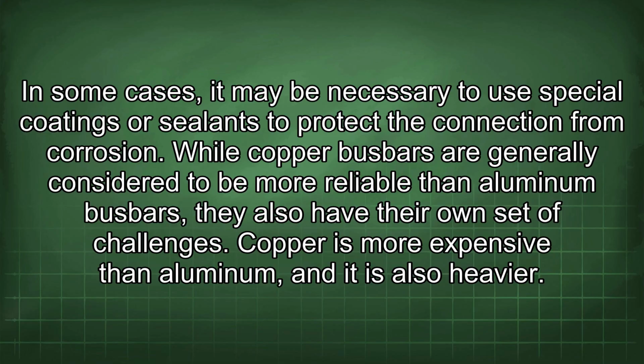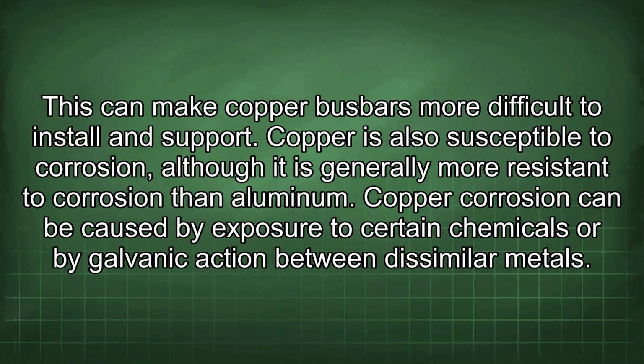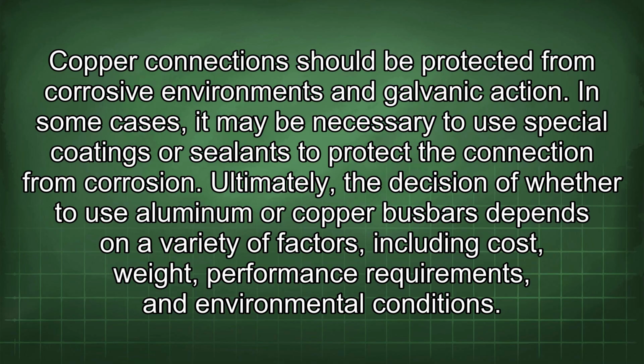While copper busbars are generally considered to be more reliable than aluminum busbars, they also have their own set of challenges. Copper is more expensive than aluminum, and it is also heavier. This can make copper busbars more difficult to install and support. Copper is also susceptible to corrosion, although it is generally more resistant to corrosion than aluminum. Copper corrosion can be caused by exposure to certain chemicals or by galvanic action between dissimilar metals. Copper connections should be protected from corrosive environments and galvanic action. In some cases, it may be necessary to use special coatings or sealants to protect the connection from corrosion.